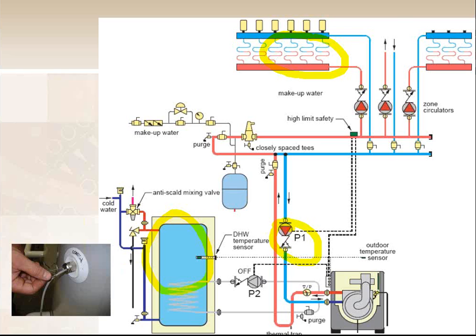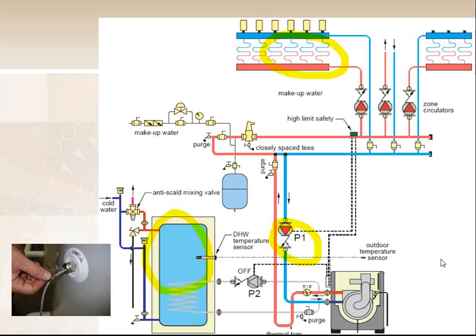The reason being is a double wall basically is a heat exchanger inside a heat exchanger. So in between there's an air pocket. If you guys do insulation work, you know that an air pocket's a fantastic insulator. So a double wall heat exchanger reduces the amount of heat transfer I can get between my boiler water and my domestic water, right? These guys right here. So I don't want to use a double wall heat exchanger unless I really need to.